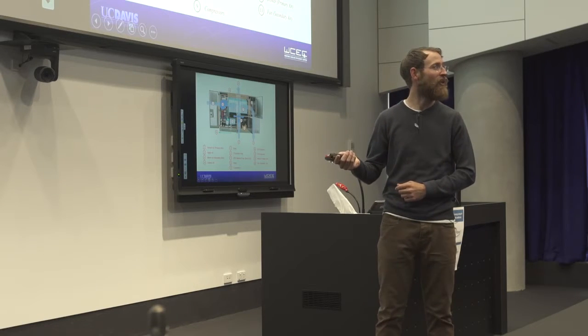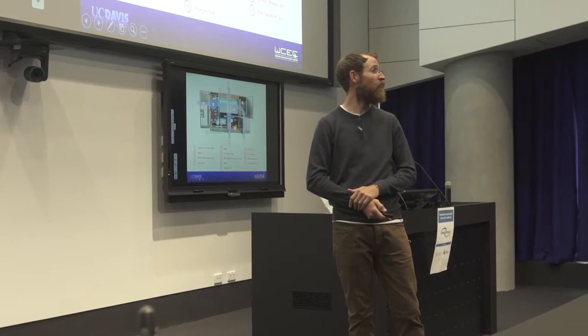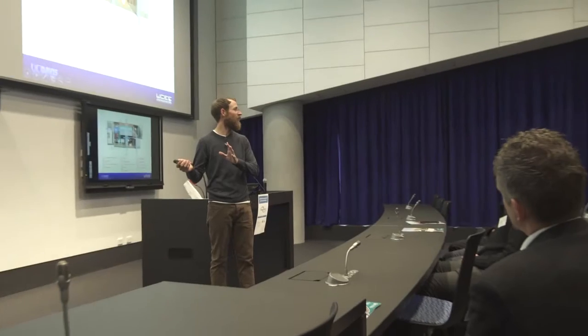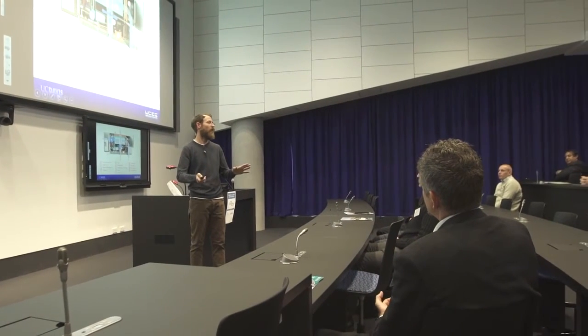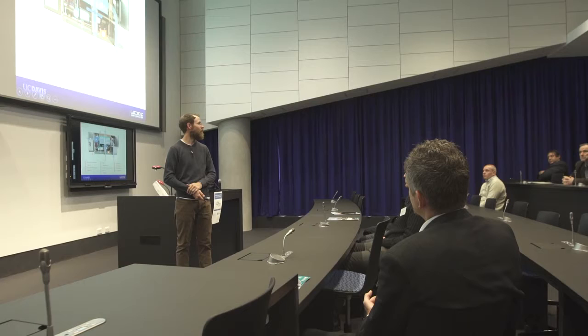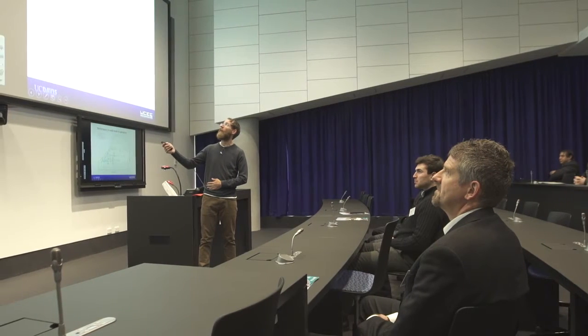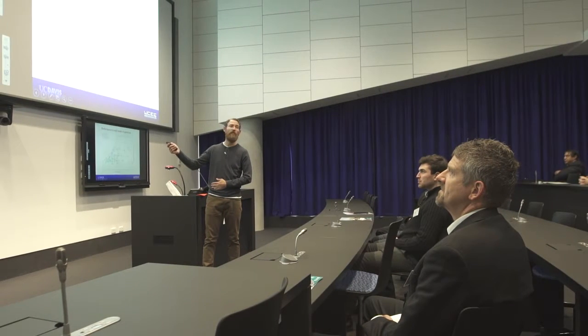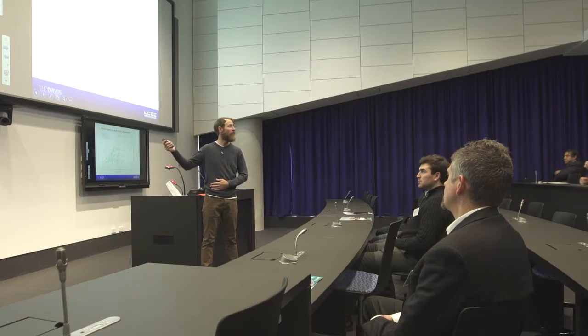So the installation that we did with Whole Foods was pretty cool to see. It's designed to supply the amount of ventilation air that was required for the space, but this system alone was able to keep the compressors from most of the other rooftop units from operating for most of the time. So there's some outstanding advantages to be had here. This is an example of the performance of that system plotted on a psychrometric chart. So you can see at what we consider our peak conditions of about 105 degrees, it's just above 40 C.